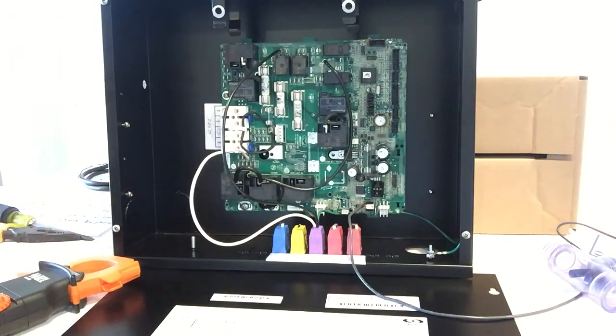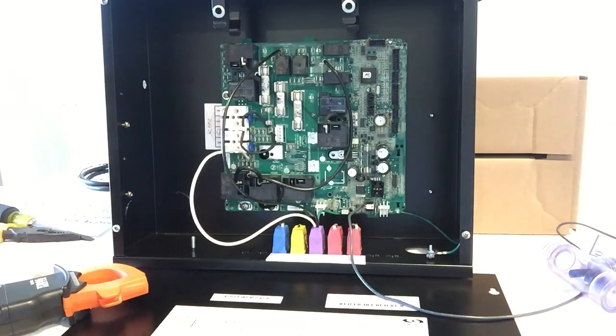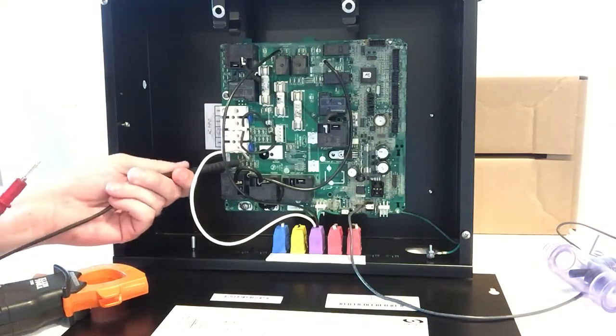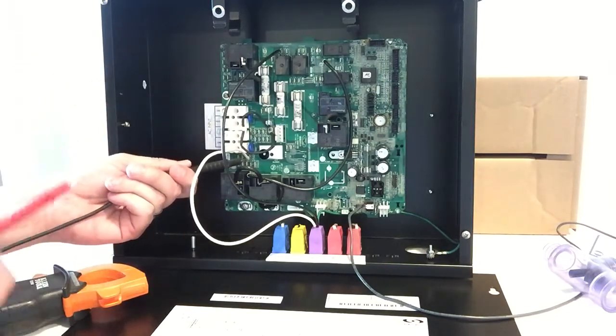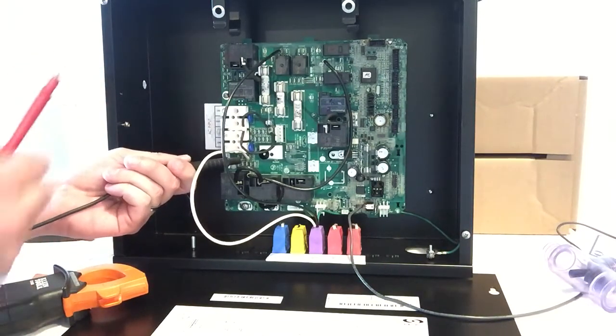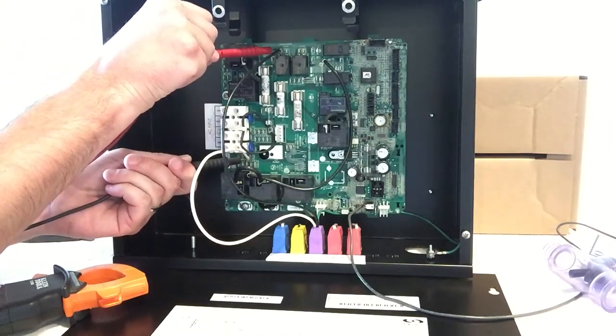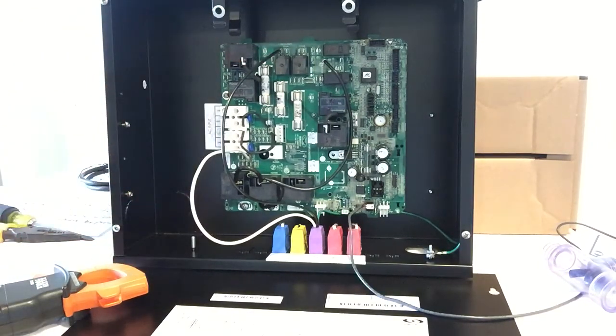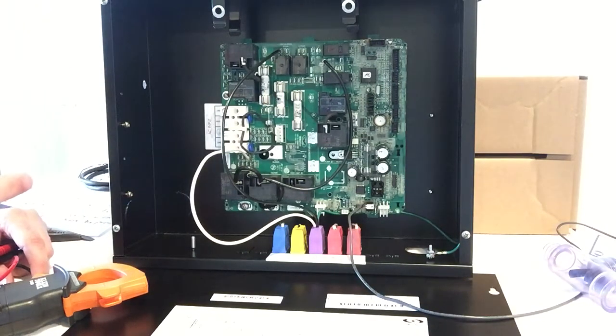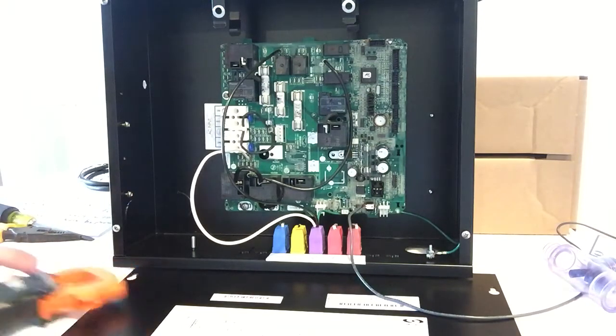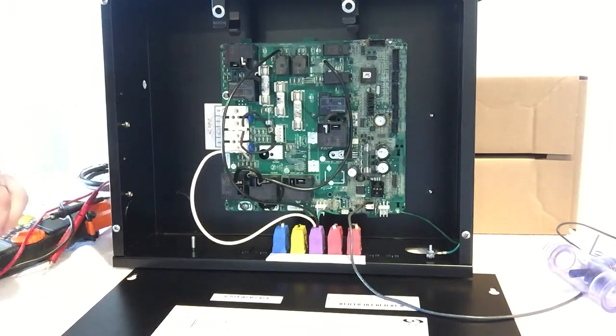Then you're going to take your meter, set it to the voltage, and carefully put one probe on the white wire and one on the black, at whether it's P41 or P54. You're going to see what your voltage reads. If you have a 120 volt pump and it reads 120, or if you have a 230 volt pump and it reads 230 on the meter, your circulation pump is bad because the PC board is sending the correct voltage to your pump. Now, that's figuring out whether your pump is good or bad.